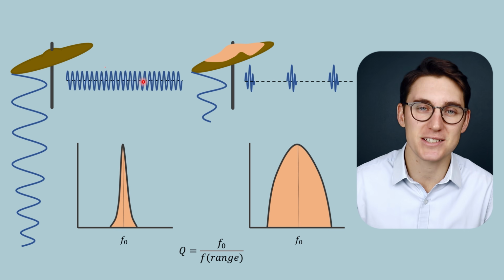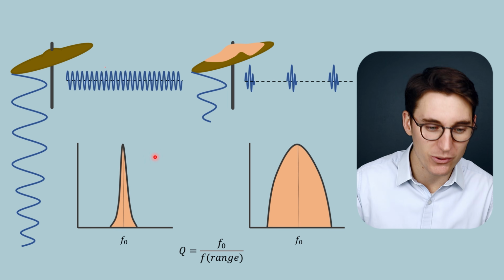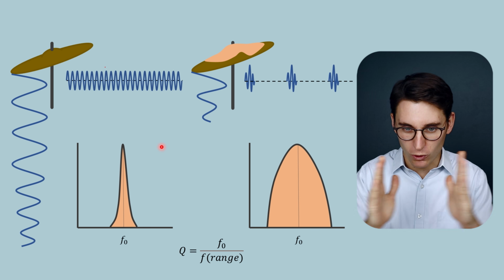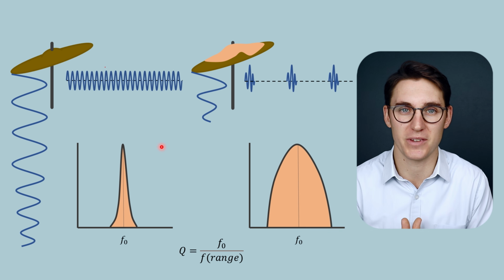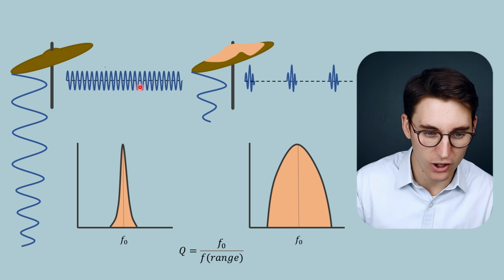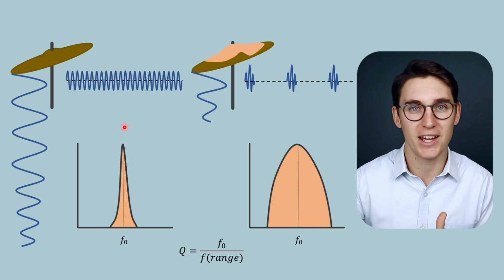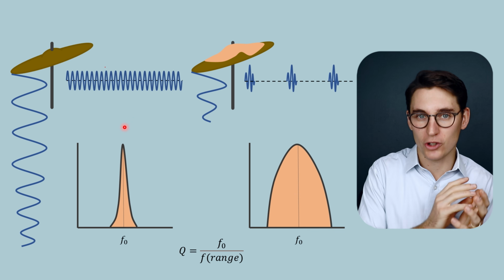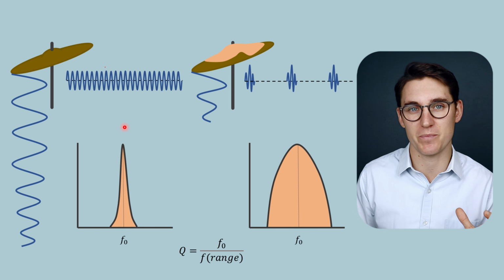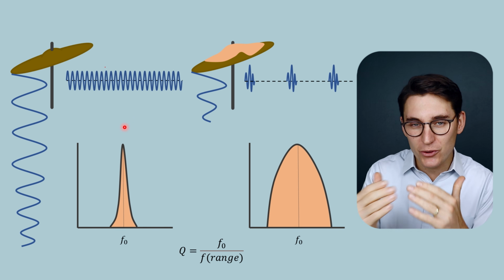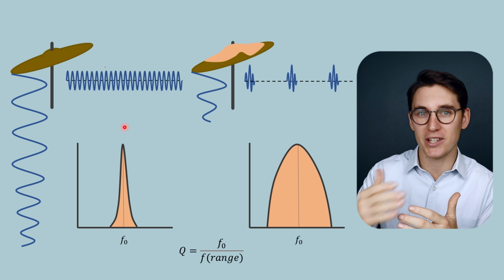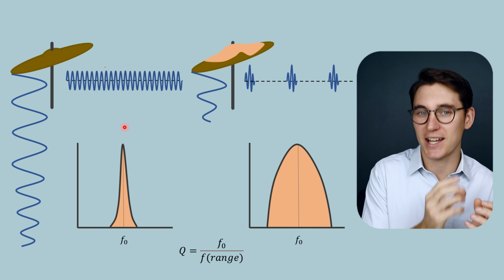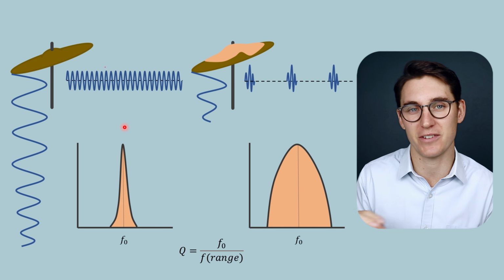The frequencies within this ultrasound wave will be very close to the resonance frequency. There'll be a very narrow range between the lowest frequency and the highest frequency. It'll all be clustering around that resonance frequency. Now, the problem with this is this long spatial pulse length, or this continuous wave, allows no time for listening for returning echoes. So we said that this is really good for Doppler imaging because we get a pure frequency. And in Doppler imaging, what we're looking at is the differences in frequencies. We're not measuring the strength of the echoes returning back. We're measuring the Doppler shift coming back and using that Doppler shift value in order to calculate the velocity values.